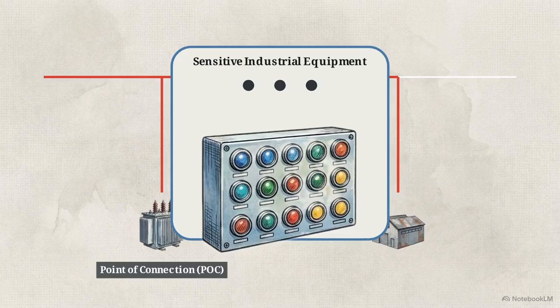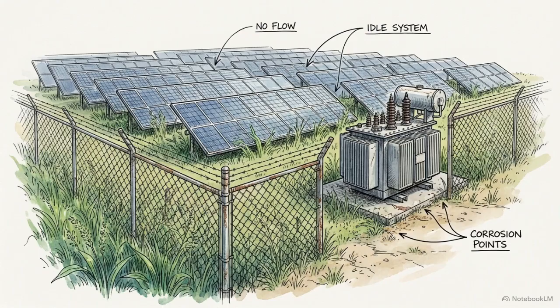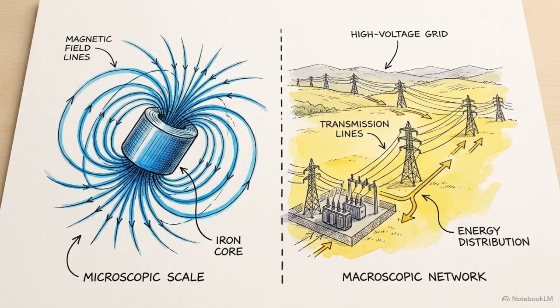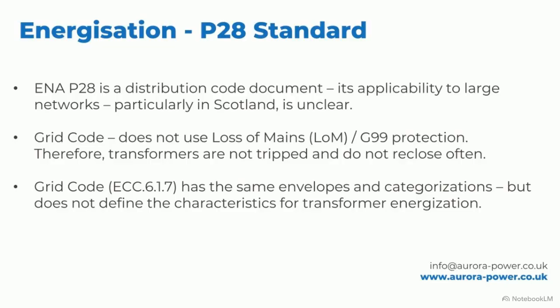facilities to trip offline. To prevent these disruptions, grid operators require rigorous power quality and compliance studies before they will grant any large generation site permission to connect. If a project fails to prove it can manage its inrush currents, it cannot be energized. The result is stranded assets, millions in frozen capital, and extensive commissioning delays. Connecting modern renewable sites means we have to accurately predict and manage the microscopic magnetic physics of individual transformers to maintain macroscopic grid stability. In the UK, the primary regulatory framework governing these voltage fluctuations is Engineering Recommendation P28.